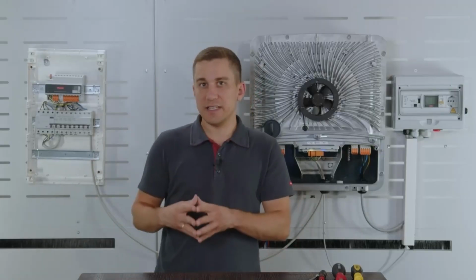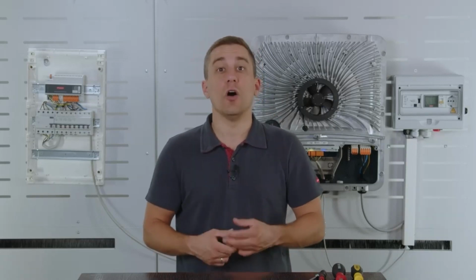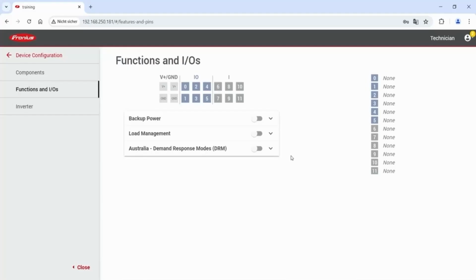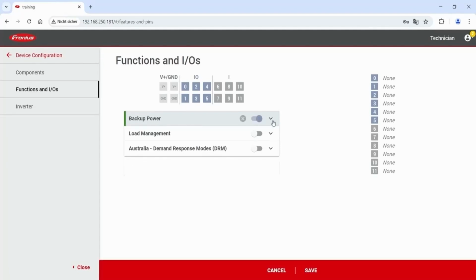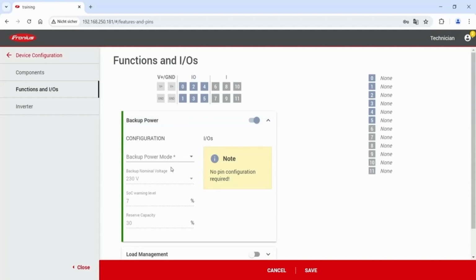The second side of installation is now the commissioning, and the commissioning of the backup power solutions I want to show you directly in our web interface of the GEN24 Plus. You start the configuration process directly under the point device configuration and then under the topic function and IOs. Please note to always log in with your technician account, since you need to be technician to alternate these settings. Down below here you find the point backup power, and we need to activate backup power functionality on the inverter with this switch here, and after that in the drop down menu you can now start the configuration.